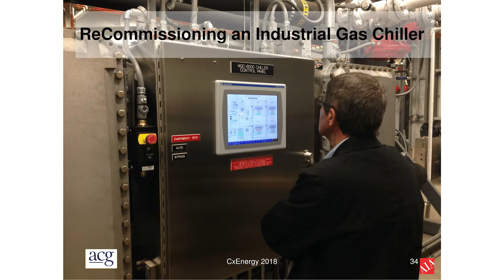We went up there. The thing was caked with ice and snow. We tarped it, we put a heat truck on it, and we leaned ladders against it to keep the tarp from blowing away. By the way, this was the worst picture I could find. There is a much better picture of the air-cooled condenser, but you've all seen one. It's just an air-cooled condenser. The difference with this one is that it has 4 completely separate refrigeration circuits in it. The design had to be modified so that they could run this thing in the winter, and the operators are going to be putting a shelter over it.